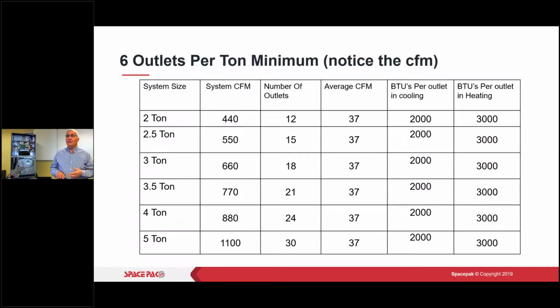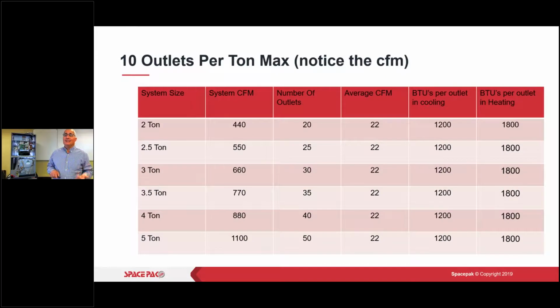So here we're showing you 6 outlets per ton. All right, you can notice how the CFM stays nice and high. So if I'm at 2 ton, we're talking 12, 2.5, 15, and so on and so forth. When I go to 10 outlets per ton, you can see now I'm up to 20 outlets on a 2 ton. Now my CFM is going to drop to 22 CFM. All right, so just be aware of these things when you're designing your systems.